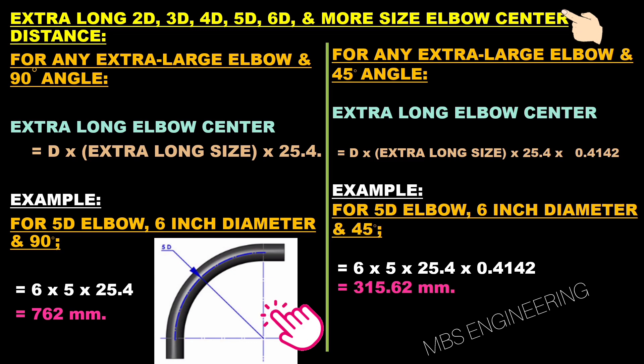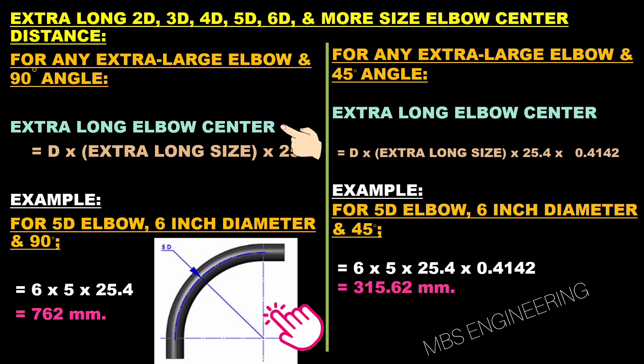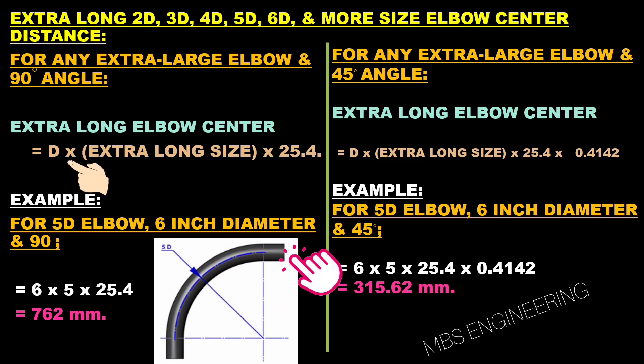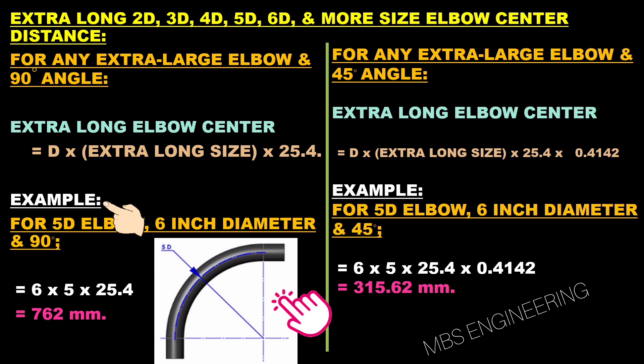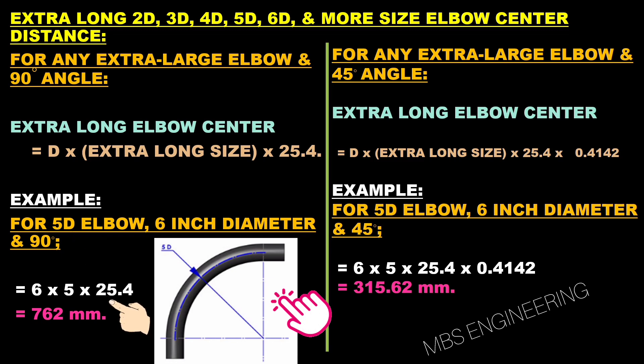Next, we will understand extra long elbow center distance calculations for 2D, 3D, 4D, 5D, 6D, and more. The formula for an extra long 90-degree elbow center distance is: Extra Long Elbow Center = D × Extra Long Size × 25.4. For example, for a 5D elbow with 6-inch diameter at 90 degrees: 6 × 5 × 25.4 = 762 millimeters.